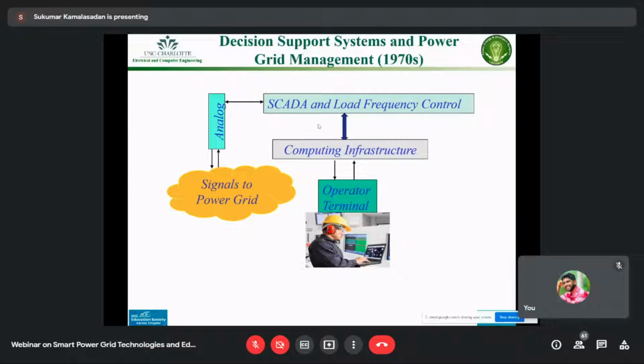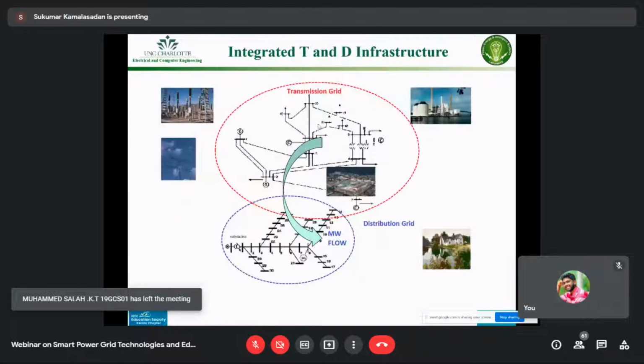The management of the power grid is done through load frequency control, which is active power management, and very little reactive power management, mainly on the power grid side for voltage stability or voltage management on the generators, called excitation system management. So what's changing now? The change is that due to the advent of renewable energy resources on the bulk power grid, we now have resources in different parts of the grid.